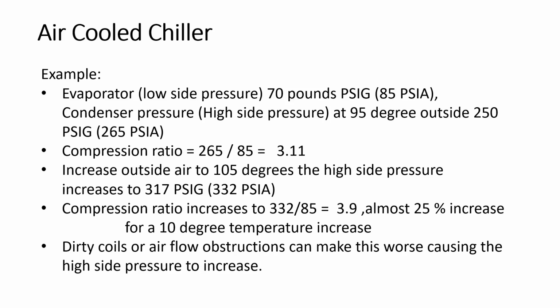Also, one of the biggest problems we have is maintenance on these. We have to keep those coils clean. And if you get any kind of newspaper or plastic shopping bags or cottonwood or anything else getting into those coils, it's going to decrease those coils' ability to reject heat, and you've got to clean them. That's a maintenance issue that's constant. Also, the wonderful children who go by a chiller sitting on the ground and carve their name into the fins has an effect also. And it's ridiculous, some of the things. I've had to spend hours combing them out.